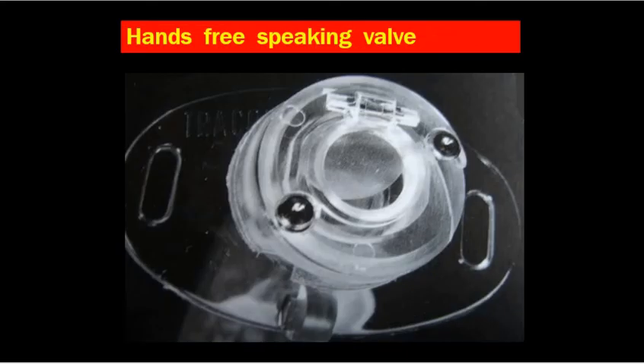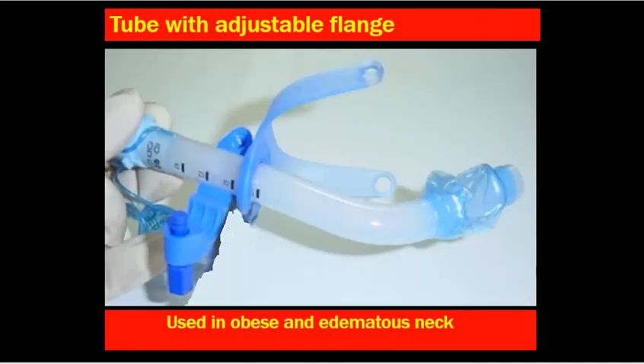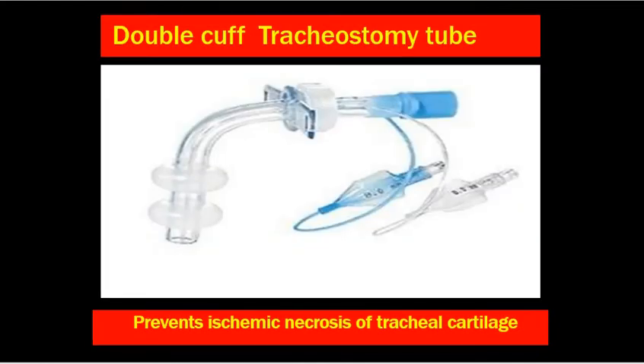There are tubes called hands-free speaking tubes. Similar to Fuller's tube where the patient closes the outer tube to speak, in the hands-free speaking valve tube, the valve closes during expiration, allowing the patient to speak through the mouth even when there is minimal airway. For obese or edematous-neck patients, tubes with adjustable flanges are used to avoid ill-fitting or displaced tubes. Double cuff tracheostomy tubes prevent ischemic necrosis of tracheal cartilage and can be used in children or those with weak trachea. Nowadays, high-volume low-pressure cuffs are standard, reducing the risk of tracheal injury.